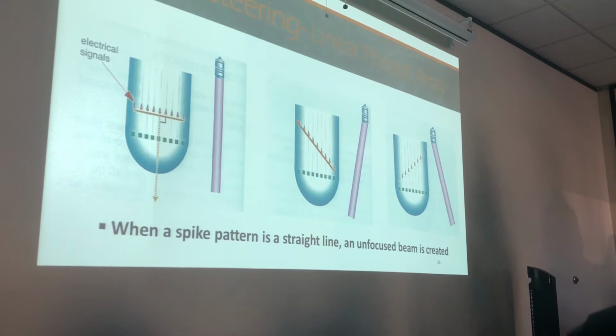The curvature, right? It has to have a curve. So that's why I said this is a straight line. It's not going to be focused, right? Because think of it. What creates focus on a conventional mechanical transducer? The internal, external. What's in common about those? It's going to be a curved active element or the curved acoustic lens, right? That's what's going to create focusing. No difference here. If we curve these electrical signals, then we're going to create focusing in this beam.